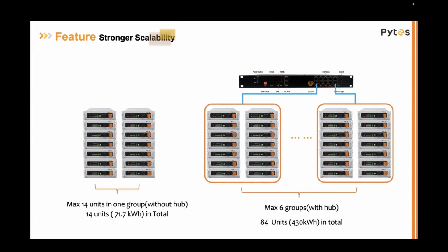Anything more than 14 units, we'll have to use the hub, which is an extra accessory. This allows us to use closed loop communications with up to 6 groups of 14, bringing us to a total of over 430 kilowatt hours in one bank of closed loop communication, as one unit. So that's some great benefits for bigger, larger projects.